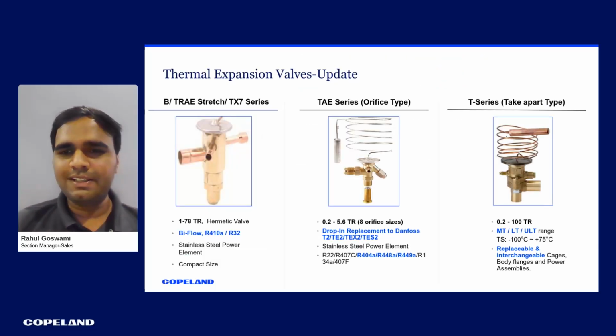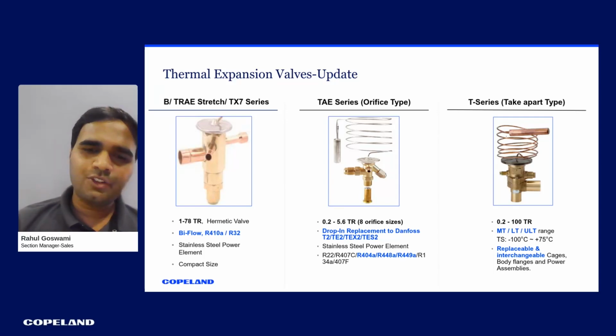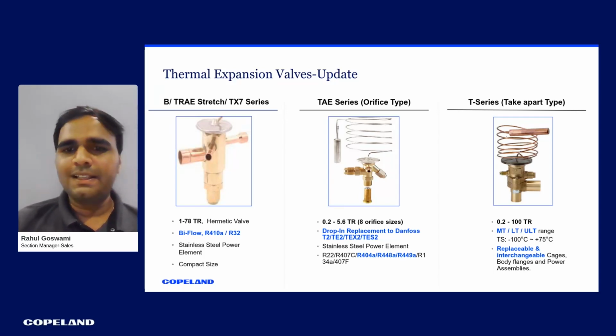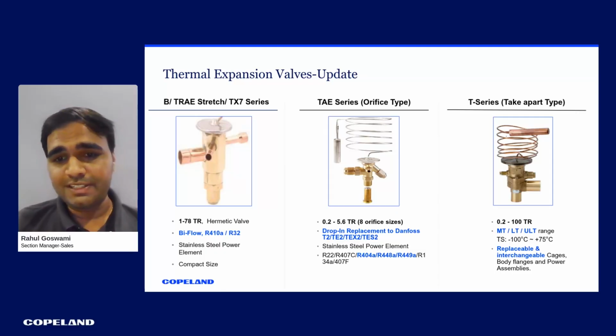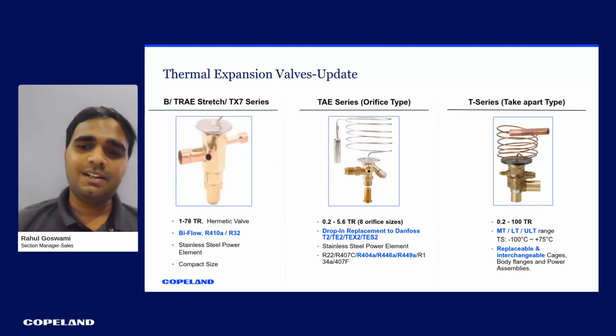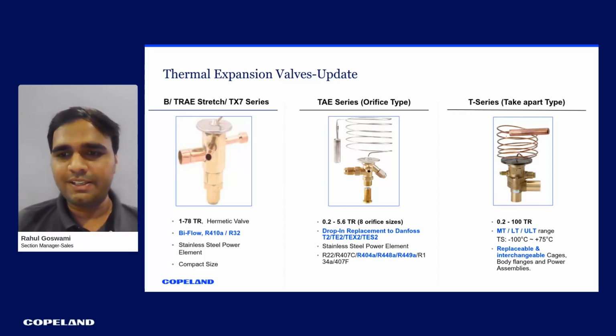So what I have explained, this is the pictorial of that. So first is welded type, hermetic type. This solution we have with the biflow technology also. Then there is TAE series, which is this orifice type. It is a drop-in replacement for the competitors' products which are available in the market. And then we have a take apart series, T series. These are used in the low temperature, medium temperature range. This is replaceable and interchangeable. You can change the cages and maintain the capacity, which will help you to keep lesser stocks of expansion valves, basically. Next slide.